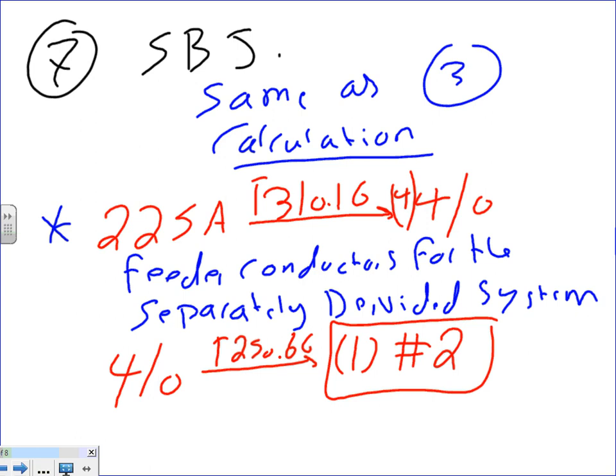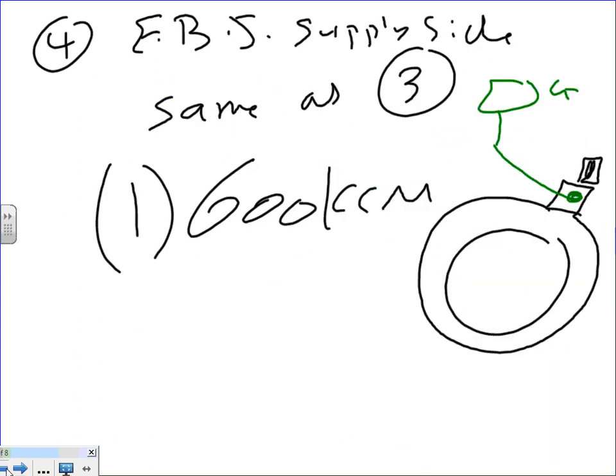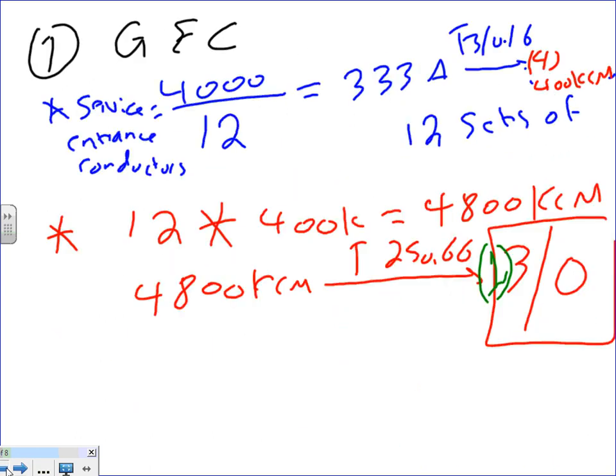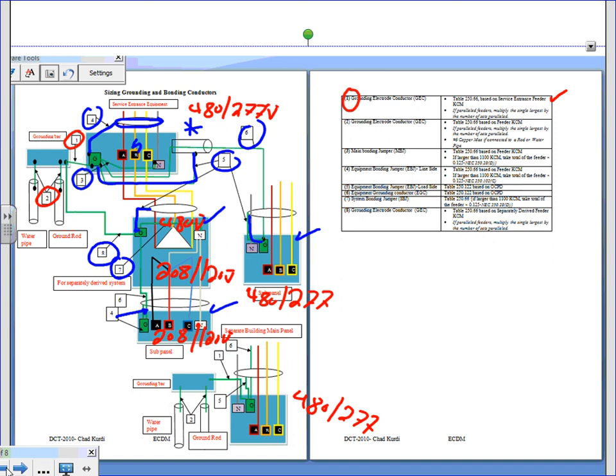And we always size it based on the secondary of the transformer, because that's what the separately derived system is. The primary is just 3 wires delta. If you guys look at, we size this based on the secondary. Look at this. Go back, Chad, here you go. Can you guys see the primary here is a delta? I don't have a neutral to tie. We created the neutral on the secondary side. Can you guys see that? Here's where neutral created, and that's where I bonded the neutral. I created the neutral on the secondary side, so I size the neutral based on the secondary of this transformer, which is in reality, it's the cables that's feeding this panel.